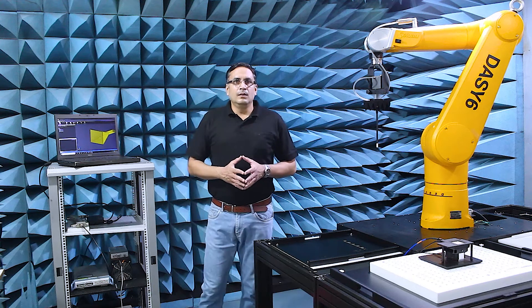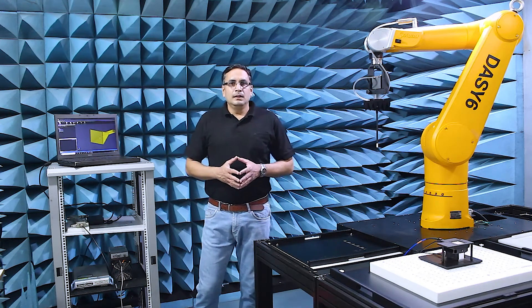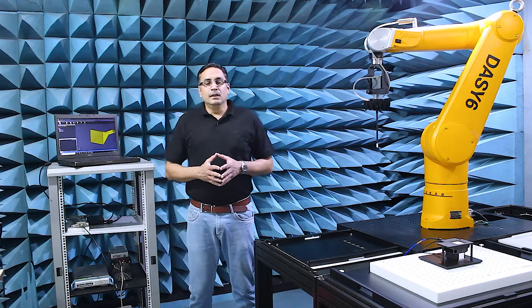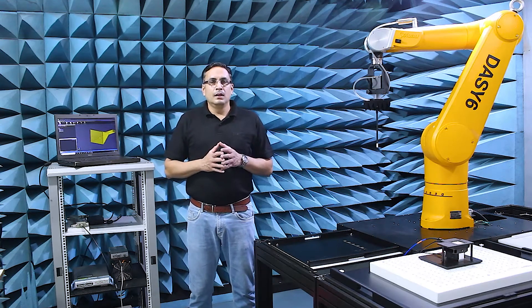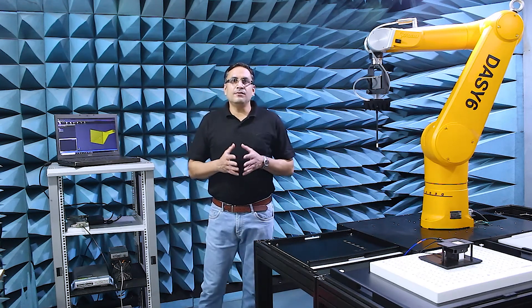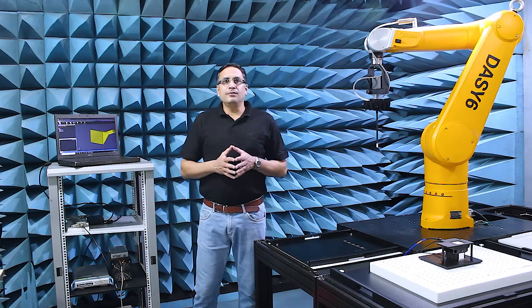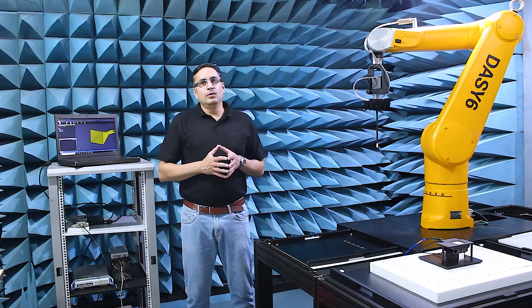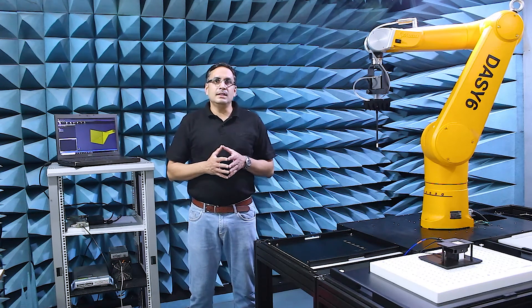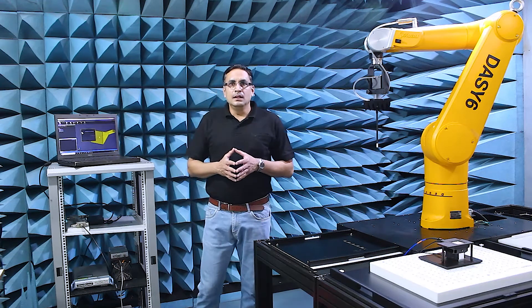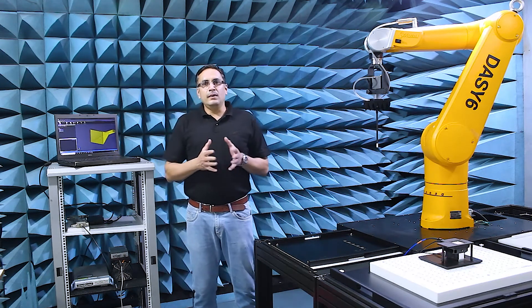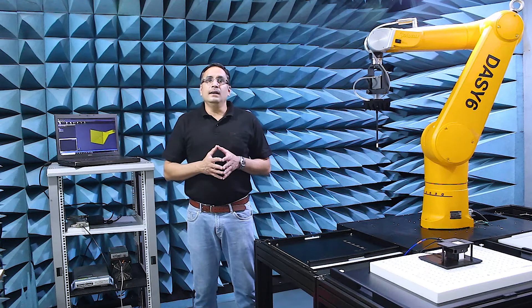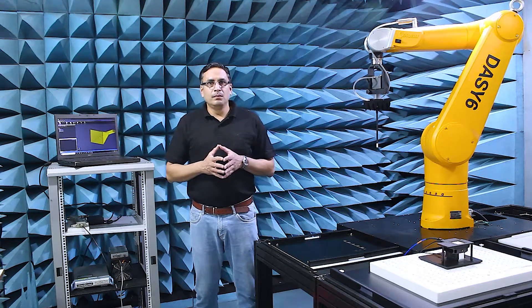Hello, my name is Nitin. The 5G network footprint is steadily increasing. Any device offering 5G new Radio FR2, which transmits at frequencies above 6 GHz, needs to be tested for power density compliance to obtain regulatory device approval.